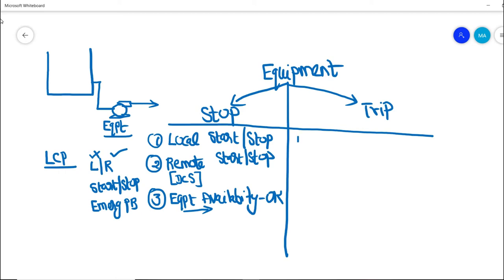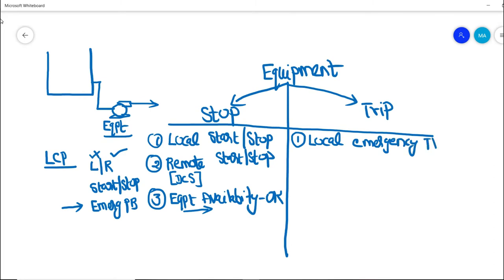Now, what is basically a trip? In the same pump example, this equipment has a local control panel with an emergency push button. If the area operator sees any process upset or abnormality happening in the field, he can immediately press this emergency push button, which will initiate an equipment trip. Local stop and local emergency trip are now different from each other.